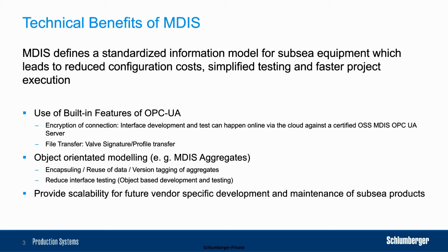The second thing that we think is good is the file transfer. In previous solutions, for example, you have to use Modbus or OPC-DA, and then for file transfer, you have to use FTP, for example. Now you have a solution that completes everything. We have the advantages of object-oriented modeling, such as aggregates, which means we can encapsulate data, we can reuse data, and we can tag data.